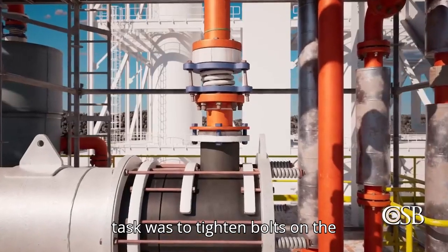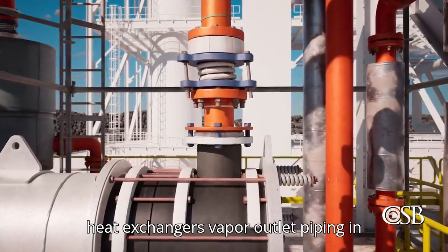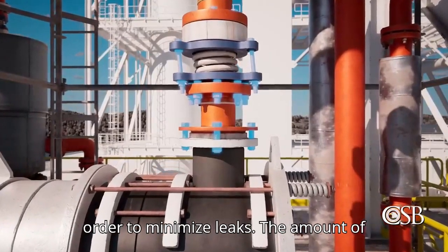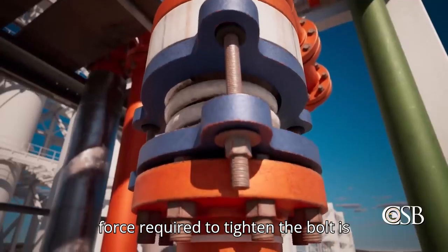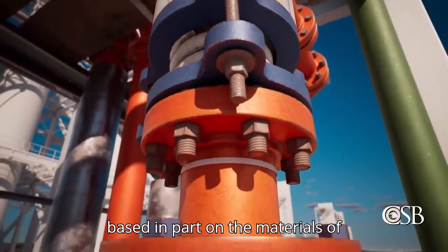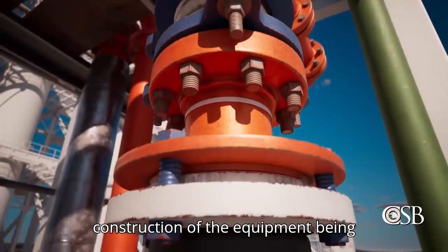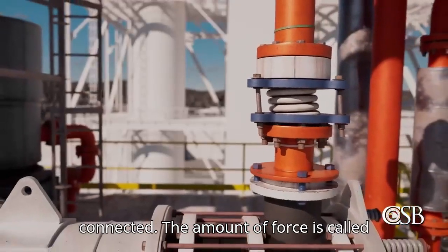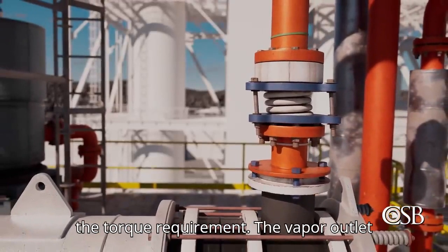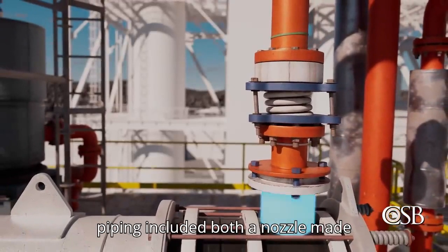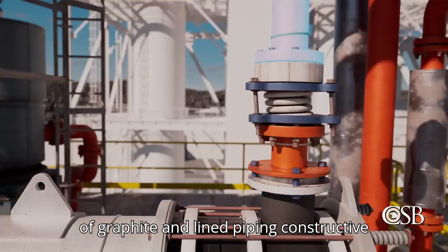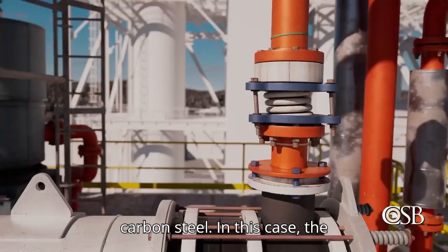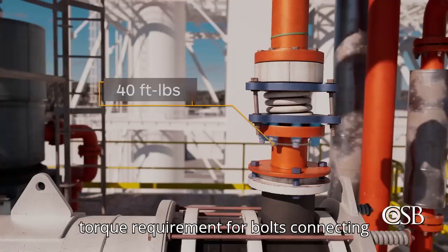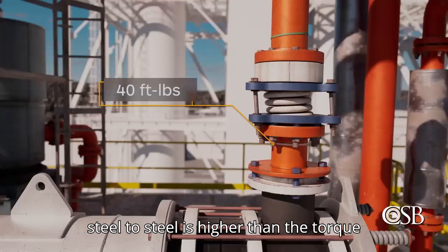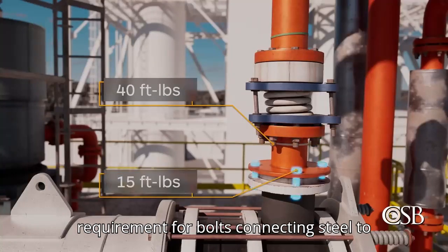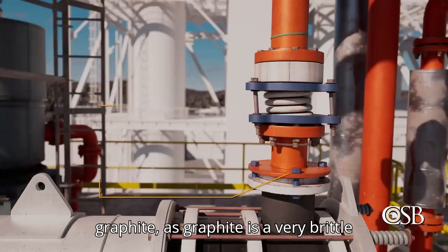The Jake Marshall contractor's task was to tighten bolts on the heat exchanger's vapor outlet piping in order to minimize leaks. The amount of force required to tighten a bolt is based in part on the materials of construction of the equipment being connected. The amount of force is called the torque requirement. The vapor outlet piping included both a nozzle made of graphite and lined piping constructed of carbon steel. In this case, the torque requirement for bolts connecting steel to steel is higher than the torque requirement for bolts connecting steel to graphite, as graphite is a very brittle material.